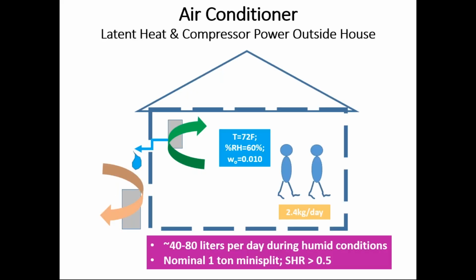As far as an air conditioner, a typical 1-ton, say, mini-split air conditioner, which is growing rapidly in homes, new homes, existing homes. These are fantastic machines, and to get more background on that, you can read our report, Minisplit Mania, which gives you much more background on how these operate. But mini splits are also good dehumidifiers, and when they're put into dry mode, they can have a sensible heat ratio down to about 0.5. And they'll pull out about 40 to 80 liters per day, depending on the humidity condition and the climatic conditions that it's working with. And so this is your first line of defense in a home.